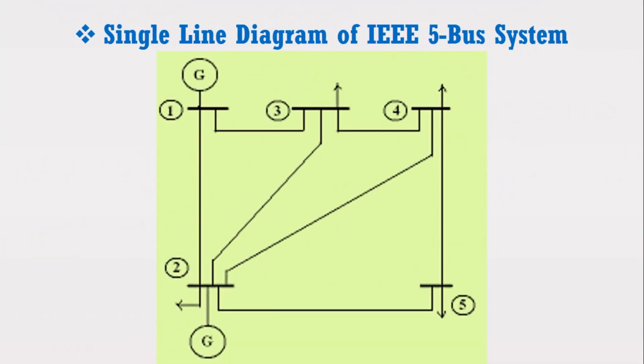Consider the figure which shows the single line diagram of IEEE 5 bus system. It can be observed that bus 1 is considered as the slack bus, and other generator as well as load is connected at bus 2, whereas all the remaining buses are load buses. We have to design the model of IEEE 5 bus system and determine the voltages at bus 2, 3, 4, and 5 using load flow analysis. Furthermore, we have to find the slack bus real and reactive power.